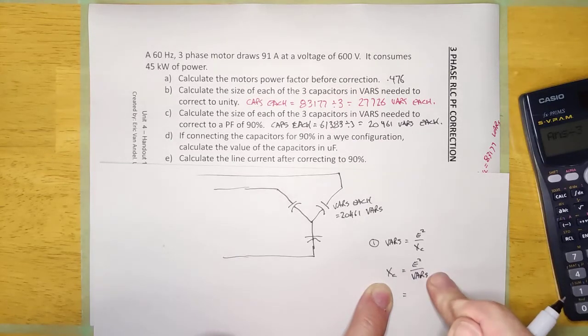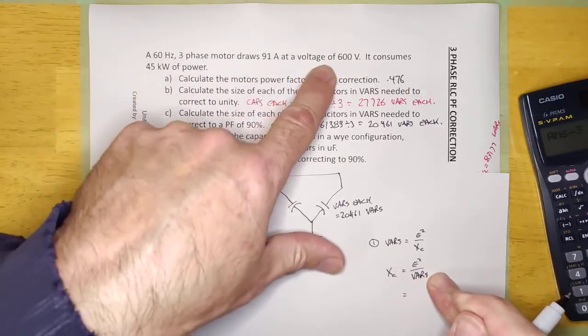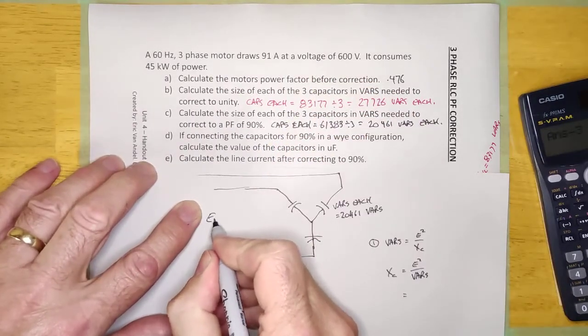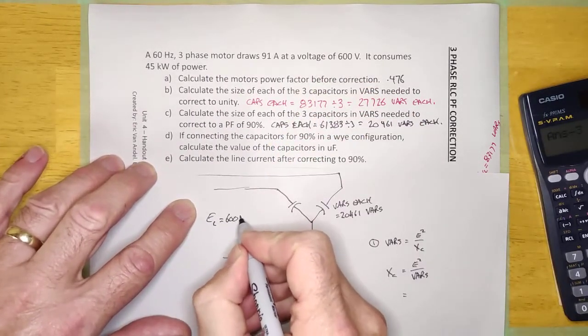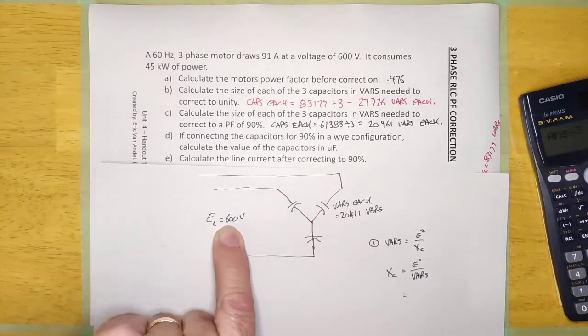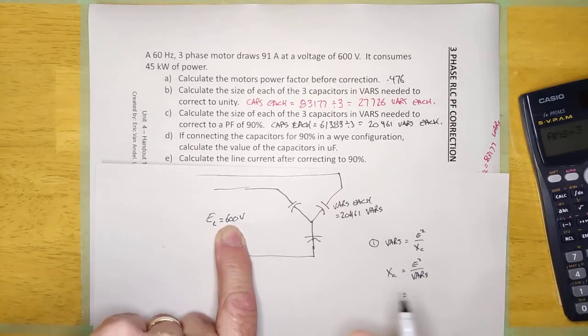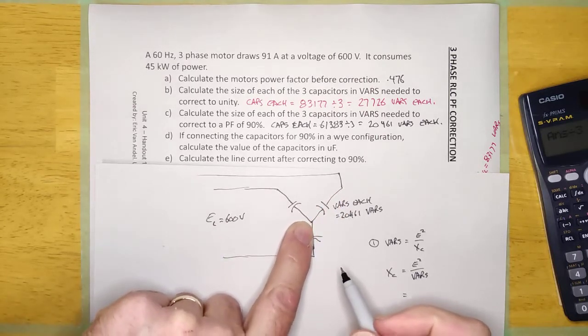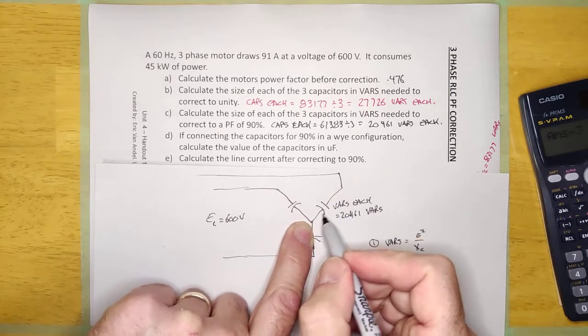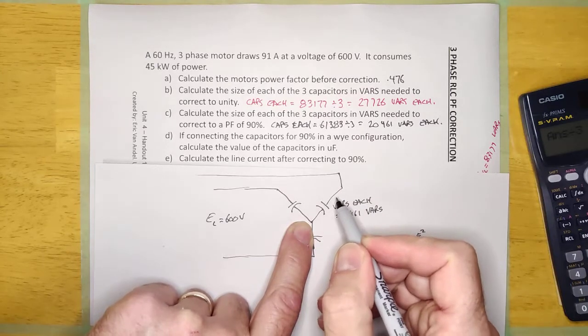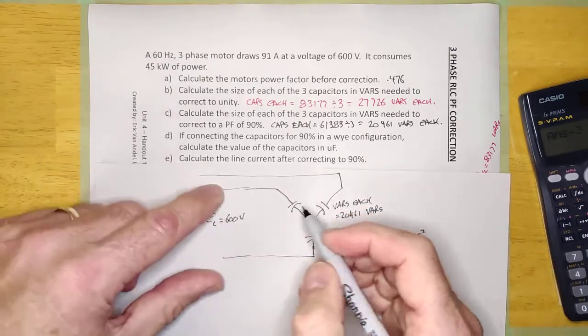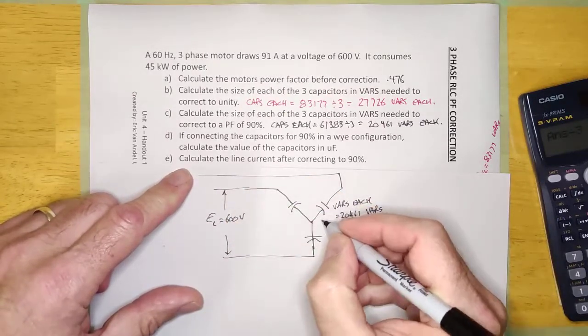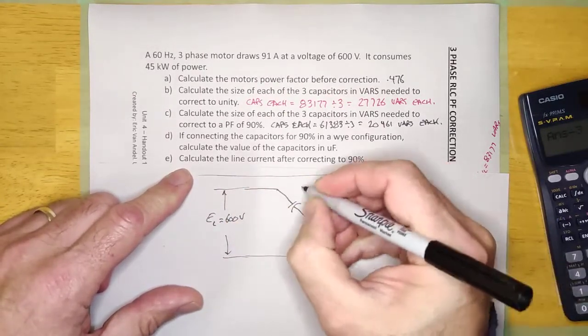Now, here's the trick here. This is 600 volts. That is the line voltage. E line is 600 volts. But I can't use 600 volts in this formula because that guy doesn't see 600 volts. It's connected Y. So, it sees 346.4, basically. If this line voltage is 600, what is the capacitor actually connected to? E phase.